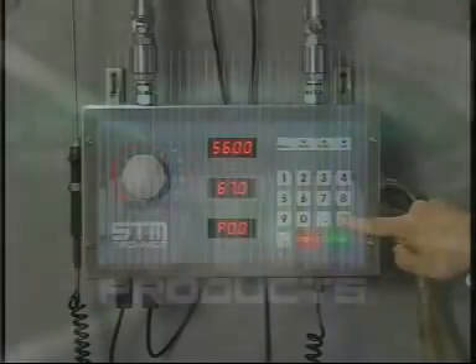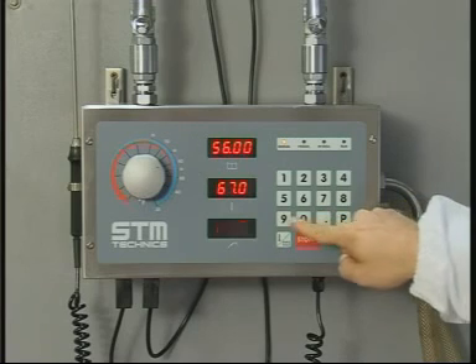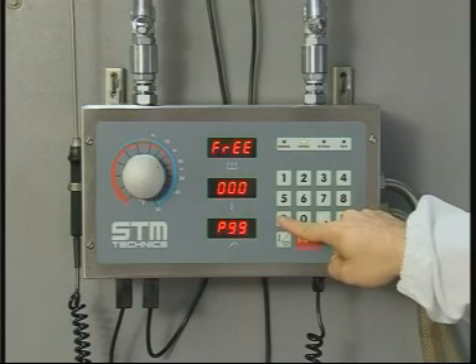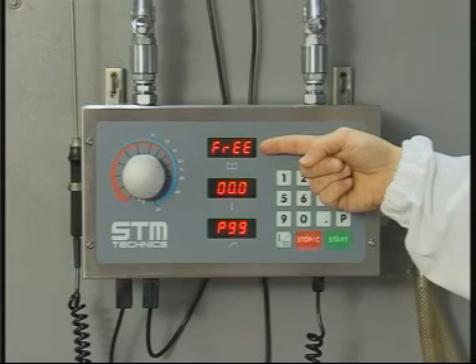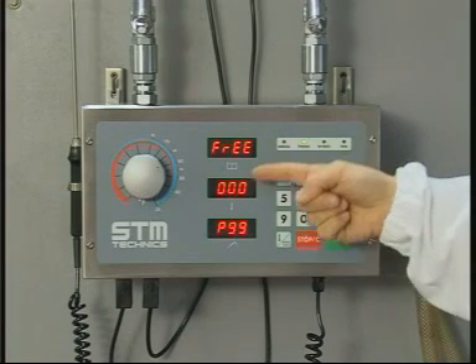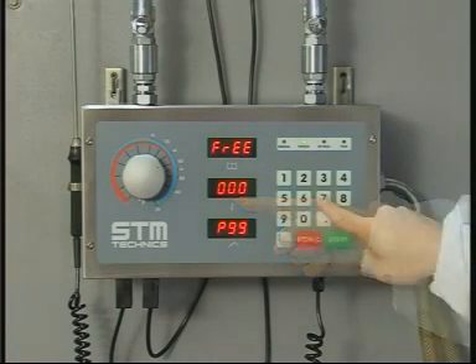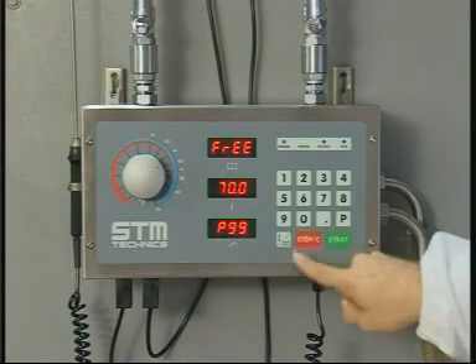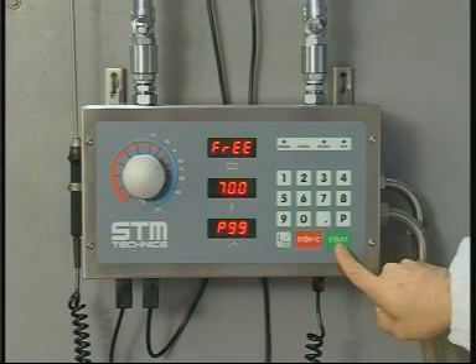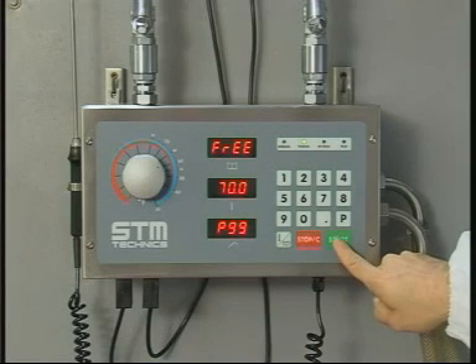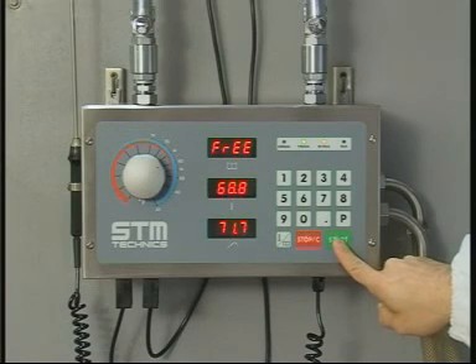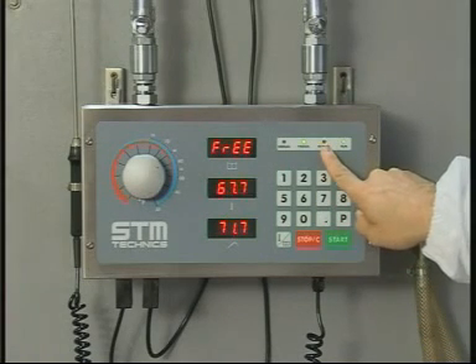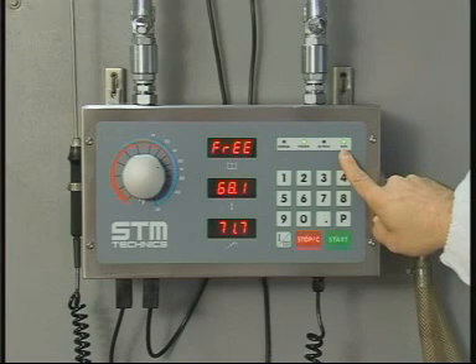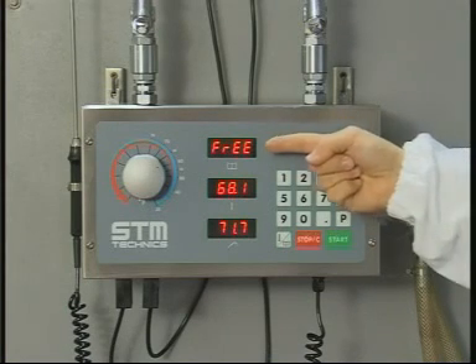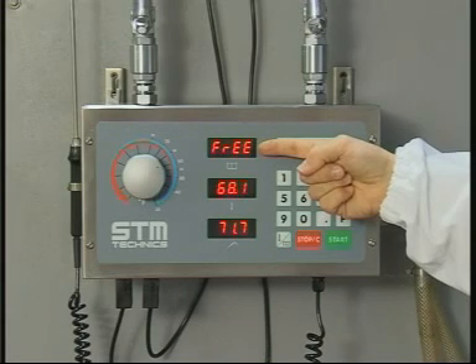Operation of free recipe. By pressing P99, one enters into the free recipe program. The writing free appears on the upper display. The desired temperature can be set on the central display. At this point, by pressing start, the machine begins to deliver at the programmed temperature, without, however, controlling the dosage. To stop the delivery, press stop.